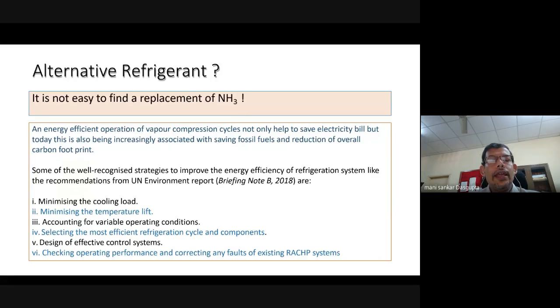Accounting for variable operating conditions is important because in most Indian cities the temperature variation may be very large, so refrigeration systems land up operating in a non-optimum condition for a large amount of the year. We have seen this for the unit in Punjab, because of the huge difference between winter and summer temperatures. Selecting the most efficient refrigeration cycle and components is also key—it may appear simple, but not much work has been done here. Many refrigeration units are copies of designs that worked elsewhere, and we have great potential to redesign them for Indian atmospheric conditions.